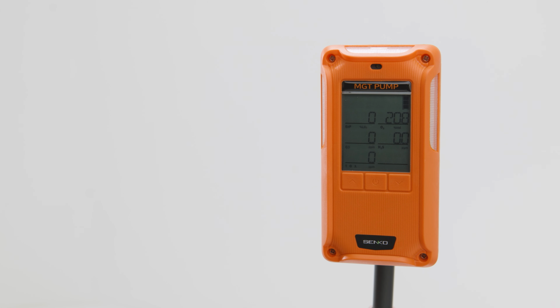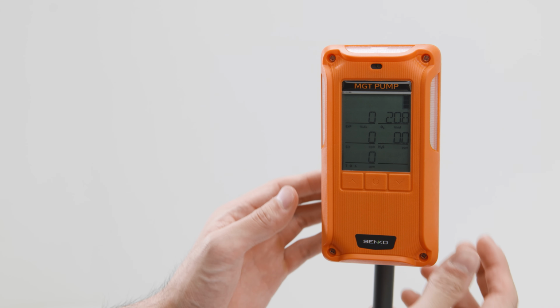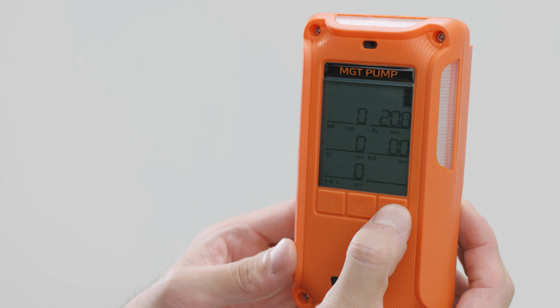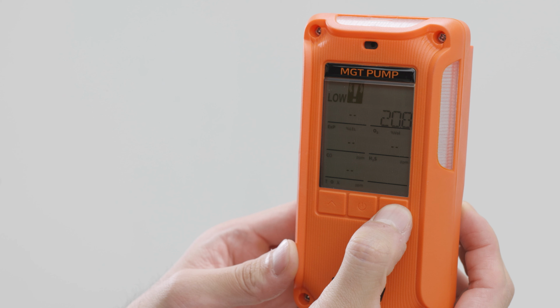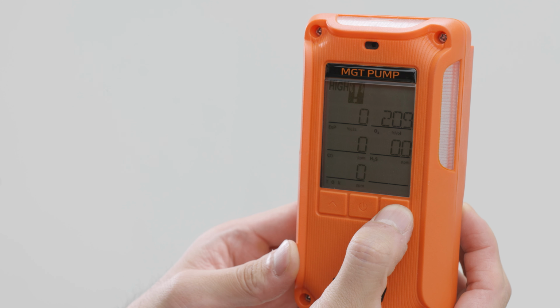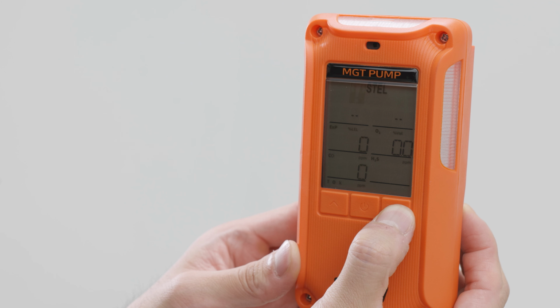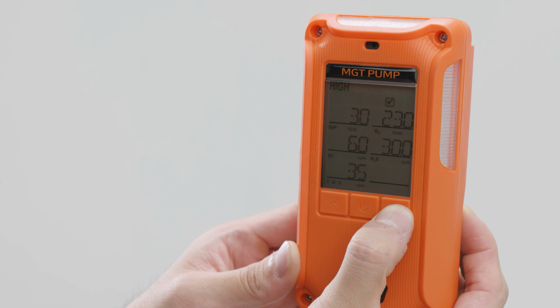In measurement mode, press the down button to view stored information sequentially. The alarm history screens appear first, showing low, high, STEL, and TWA values. These allow you to review the minimum and maximum recorded gas concentrations, as well as short-term exposure and time-weighted average values. For a new device, it is normal for gases other than oxygen to show no recorded values.